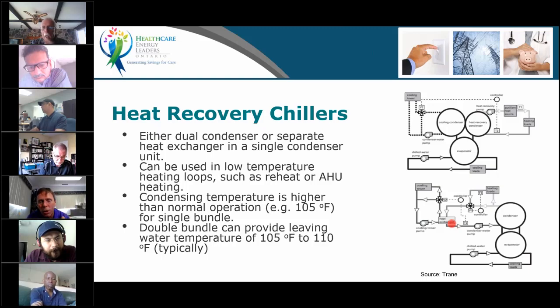Ideally, you would send that water to, let's say, radiation heaters, but also to makeup air units or air handling coils, which are low temperature coils. Those can actually heat because they usually do air preheating, or they are tempering the air to about 70 degrees Fahrenheit or so. So those are good loads to send the heat recovery heat into. Reheat loops are also very often used with the heat recovery chiller because they are low temperature loops. Those heat recovery chillers are basically heat pumps. In the winter time, they take the internal heat and send it to the perimeter. So it's basically a central heat pump that you use in the winter.